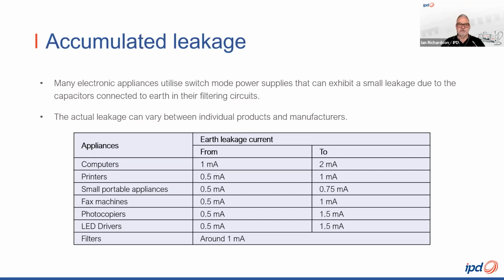You know, Fred, I find this table really interesting. Over the years, I've had many contractors say that the RCD is tripping for no apparent reason. They tell me they've checked the load, it's a 16 amp RCBO, they're only pulling 5 or 6 amps, and this rotten RCBO trips.